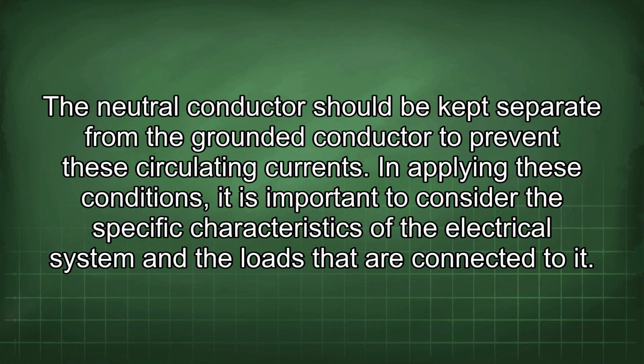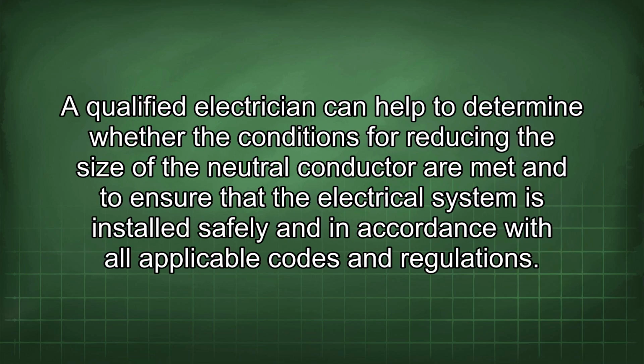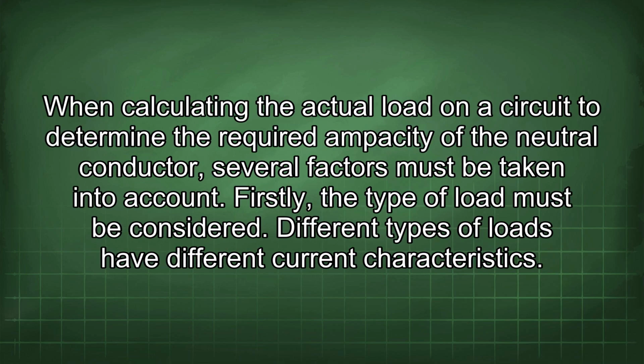In applying these conditions, it is important to consider the specific characteristics of the electrical system and the loads that are connected to it. A qualified electrician can help to determine whether the conditions for reducing the size of the neutral conductor are met and to ensure that the electrical system is installed safely and in accordance with all applicable codes and regulations. When calculating the actual load on a circuit to determine the required ampacity of the neutral conductor, several factors must be taken into account.